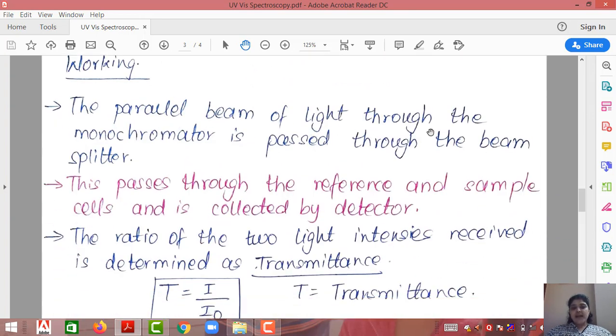Now the working: The parallel beam from the monochromator passes through the beam splitter, through the reference and sample cells, and is collected by the detector. When light strikes the sample or reference cell, a part of it is absorbed and a part is transmitted. 100% light will never be fully absorbed nor fully transmitted. Absorption depends upon the concentration of the cell — higher the concentration, higher the absorption, and therefore lower the transmittance.